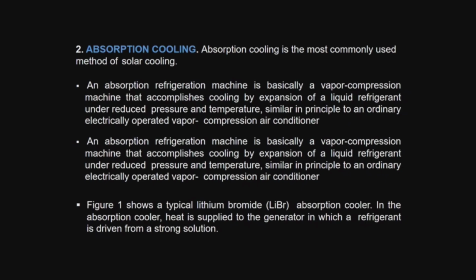Absorption cooling. Absorption cooling is the most commonly used method of solar cooling. An absorption refrigeration machine is basically a vapor compression machine that accomplishes cooling by expansion of a liquid refrigerant under reduced pressure and temperature, similar in principle to an ordinary electrically operated vapor compression air conditioner.